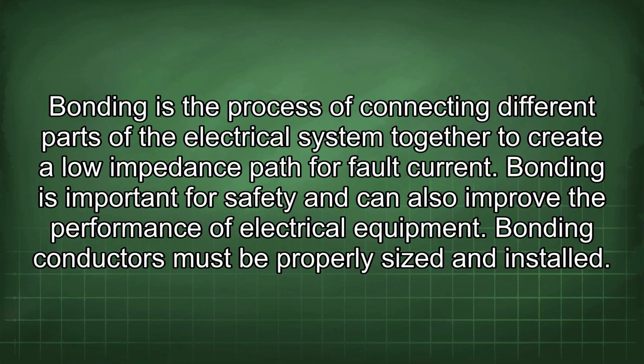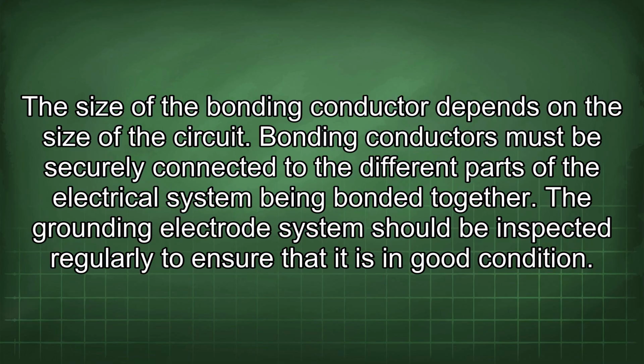Bonding is the process of connecting different parts of the electrical system together to create a low impedance path for fault current. Bonding is important for safety and can also improve the performance of electrical equipment. Bonding conductors must be properly sized and installed. The size of the bonding conductor depends on the size of the circuit. Bonding conductors must be securely connected to the different parts of the electrical system being bonded together.